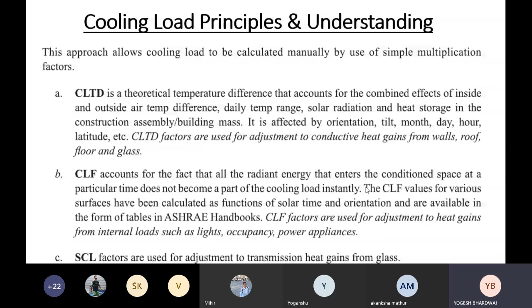Okay, now we can see on this slide how much heat will come into my room through walls, floors, and roofs. So this formula, Q is equal to U A CLTD, is basically derived from Q is equal to m c delta T only. Here Q is the heat in BTU per hour. I told you we are using IP units. U is in BTU per hour per square foot per degree Fahrenheit. Area is the total area of that particular assembly for which we are using this U value.